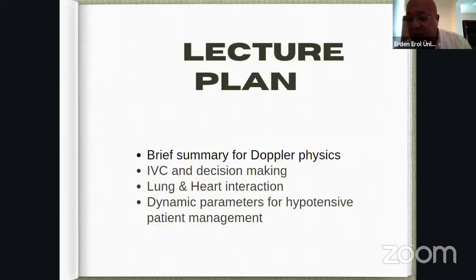So this is important because when the angle of the transducer goes over 60 degrees, the cosine will be closer to zero. And if you put a zero value here, you will again get a zero number. So the velocity will be zero if the angle of the transducer is closer to 90 degrees. So you should be as parallel as you can while you are measuring the velocity of blood flow. This is very important. Because of that, we are trying to be as parallel as possible to the blood flow.